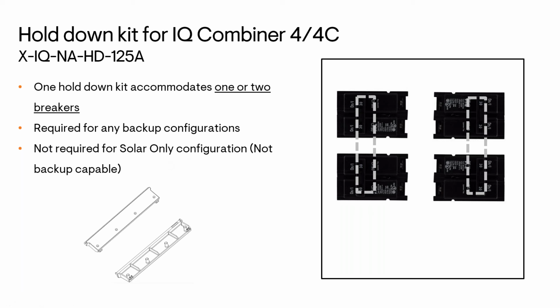Again, these must be installed and breakers bolted down whenever the combiner is being used in a backup configuration. Compatible breakers, which have the required hole for the bolt, are listed in the tech brief, which I'll make sure that you have a link to at the end of this session.